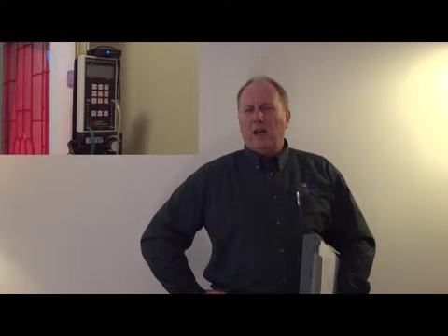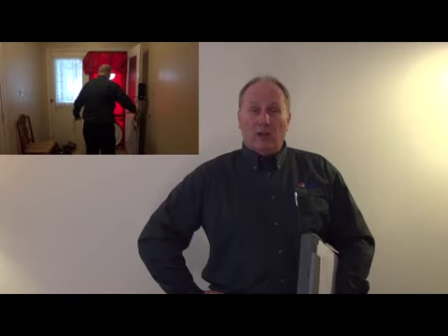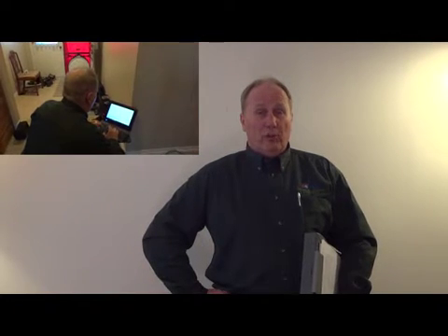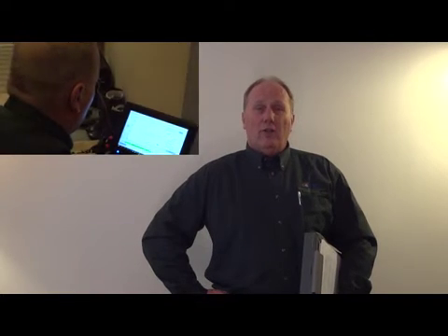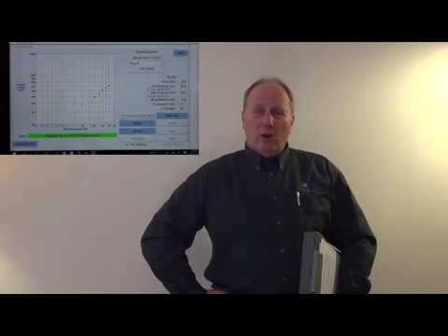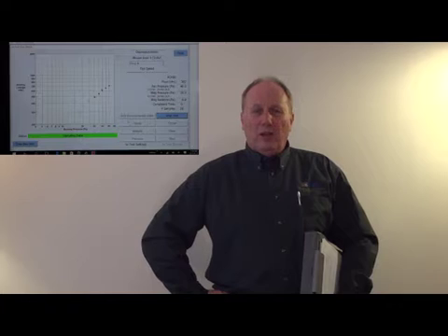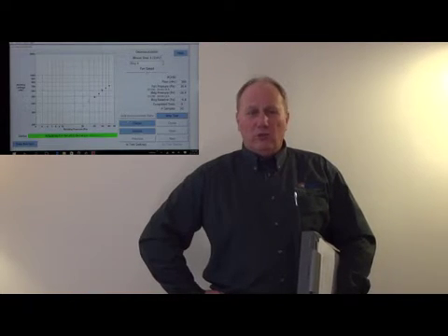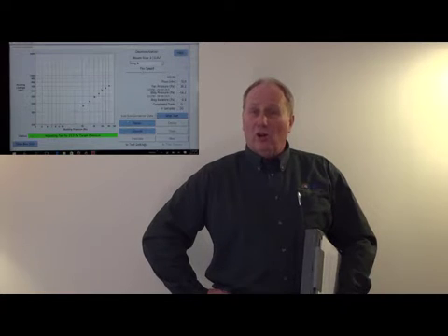It's controlled by a manometer. The manometer is connected up to the blower door, and it's also connected up to a tablet computer that controls the manometer, controls the flow that's happening between the inside and the outside of the home. The software is written by the hardware manufacturer, so you get the best possible results. We begin the test at 50 pascals, which in real terms means about a 30-mile-an-hour wind hitting your house at all angles at the same time, something that doesn't happen in nature.